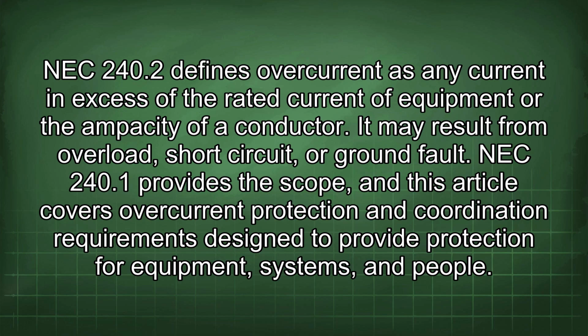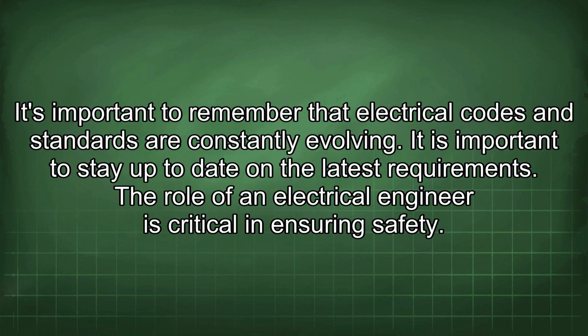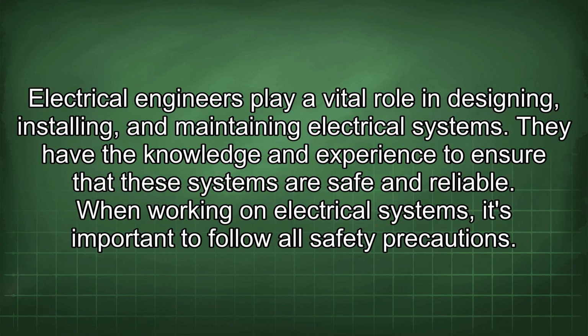NEC 240.2 defines overcurrent as any current in excess of the rated current of equipment or the ampacity of a conductor. It may result from overload, short circuit, or ground fault. NEC 240.1 provides the scope, and this article covers overcurrent protection and coordination requirements designed to provide protection for equipment, systems, and people. It's important to remember that electrical codes and standards are constantly evolving. It is important to stay up to date on the latest requirements. The role of an electrical engineer is critical in ensuring safety. Electrical engineers play a vital role in designing, installing, and maintaining electrical systems. They have the knowledge and experience to ensure that these systems are safe and reliable.